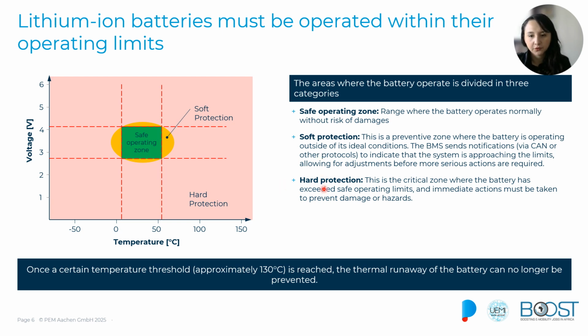as was explained before. But also in this type of diagram we can visualize and represent, for instance, soft protections. The soft protections act as preventive measures, and when the battery is approaching those dangerous boundaries, the BMS issues warnings and adjusts operation, for example, reducing the charging current or turning on the heating system, or turning on the cooling system to prevent that we get to those unsafe conditions.